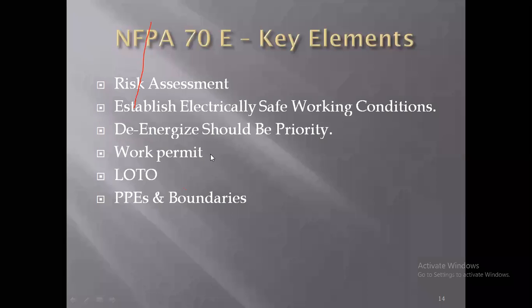De-energize. NFPA says that while performing electrical tasks, your priority should be to de-energize your equipment - it shouldn't be energized. Why? Because risk is increased many times over with an energized, charged line or equipment. So companies adopting NFPA70E must keep in mind that for the majority of electrical tasks, de-energizing should be their priority. They must not put their workers at risk - in order to protect their workers, they must adopt and implement a de-energize policy.